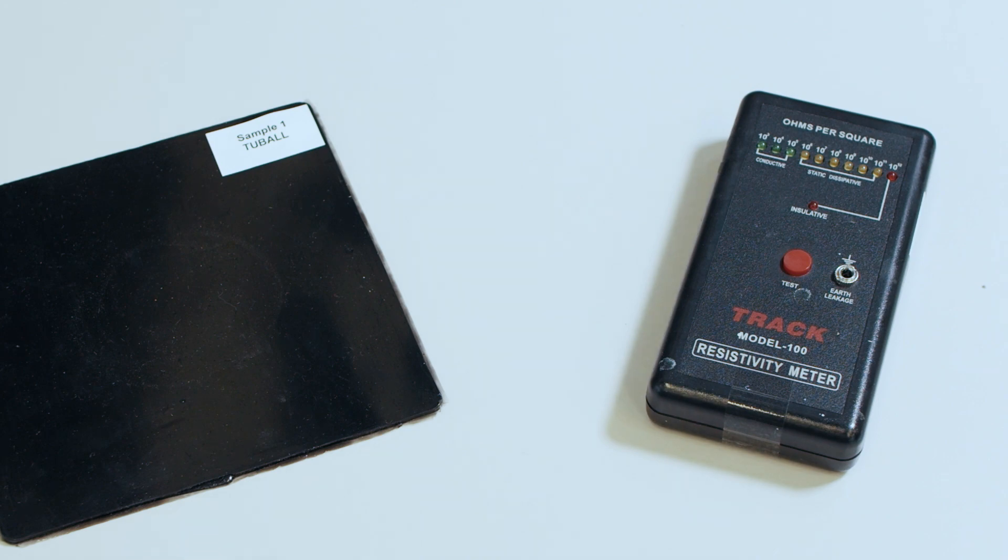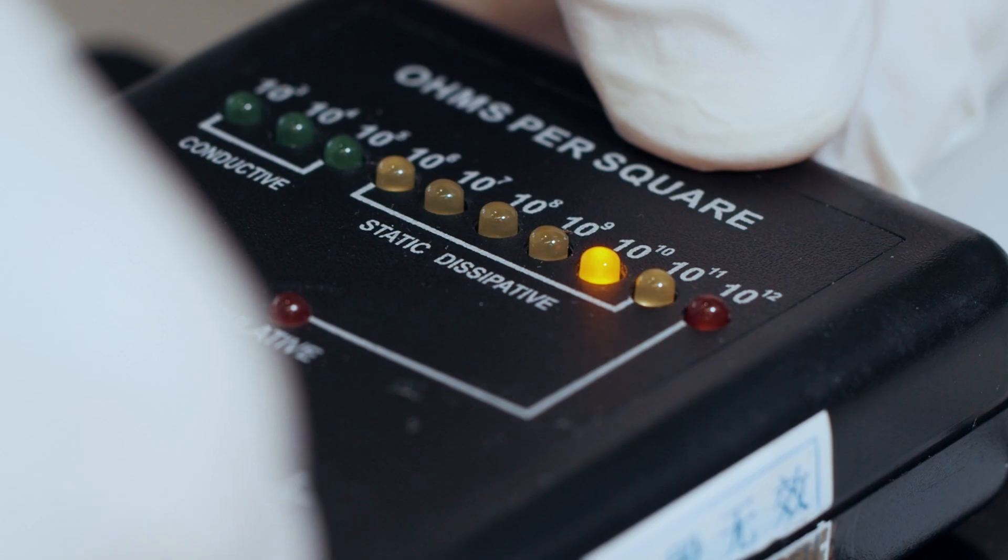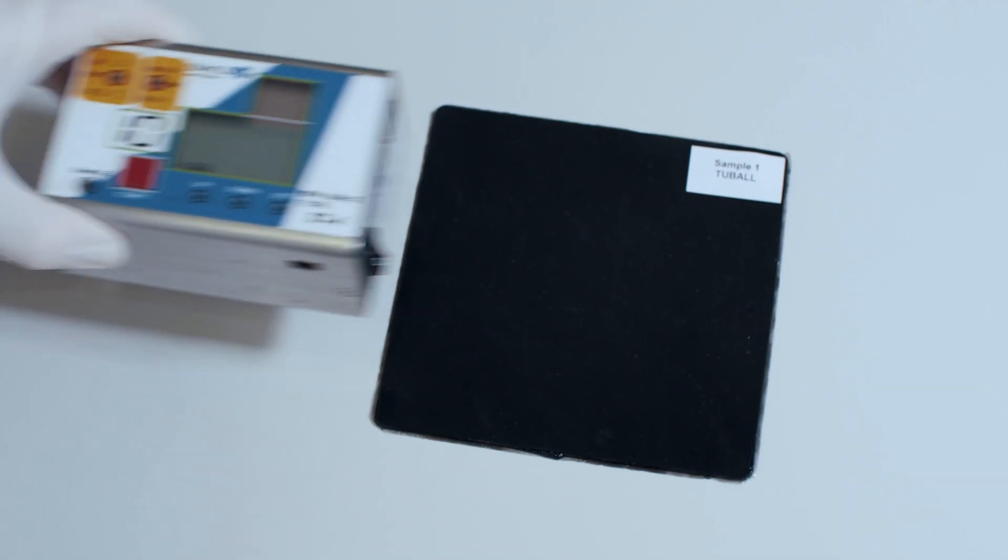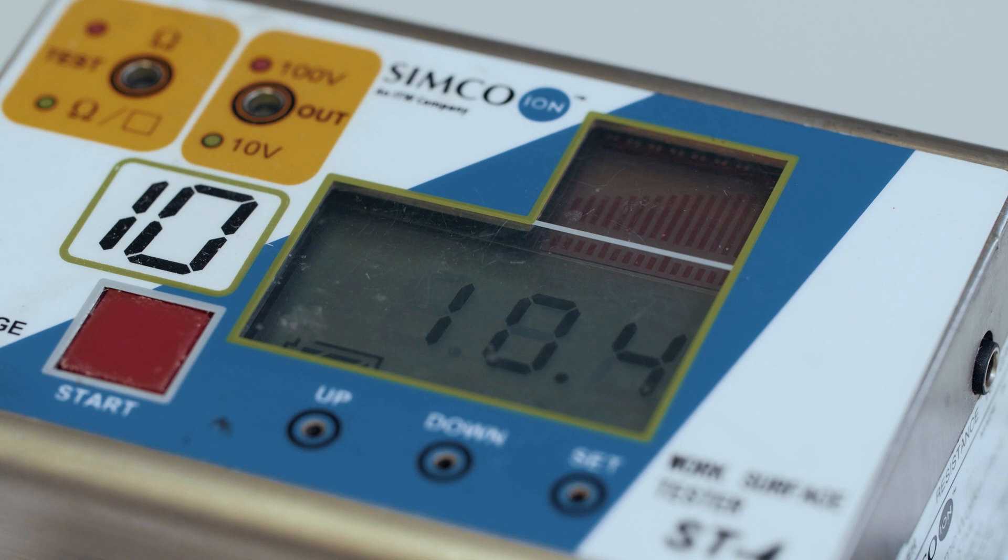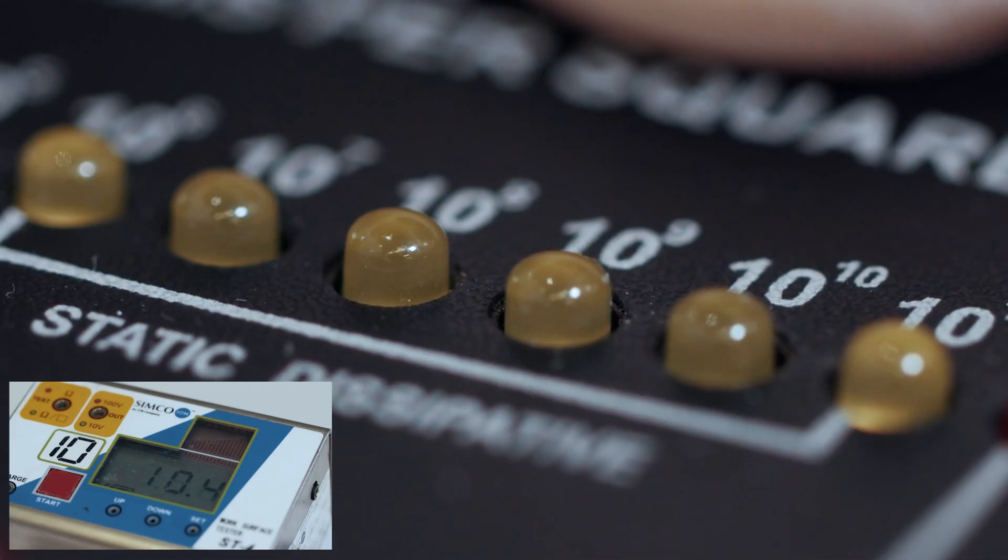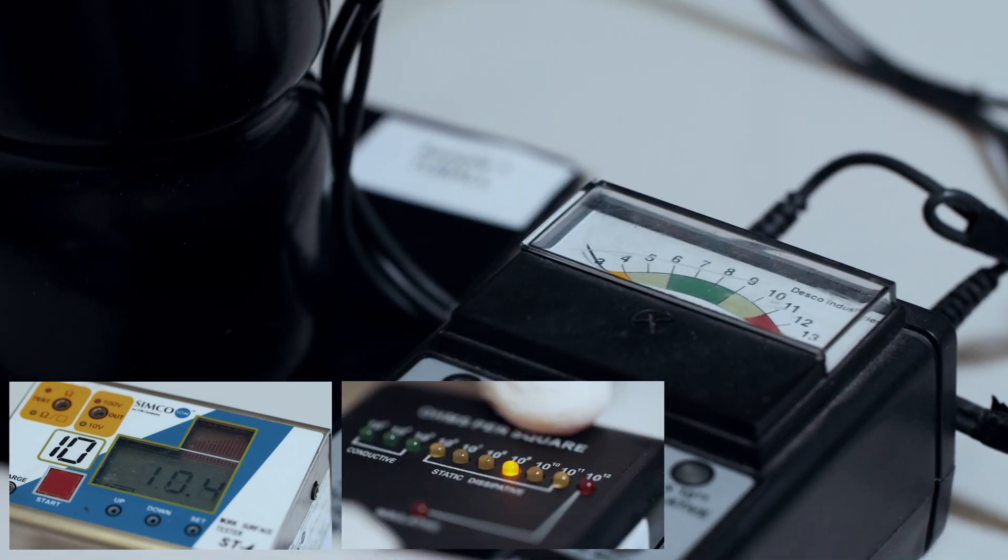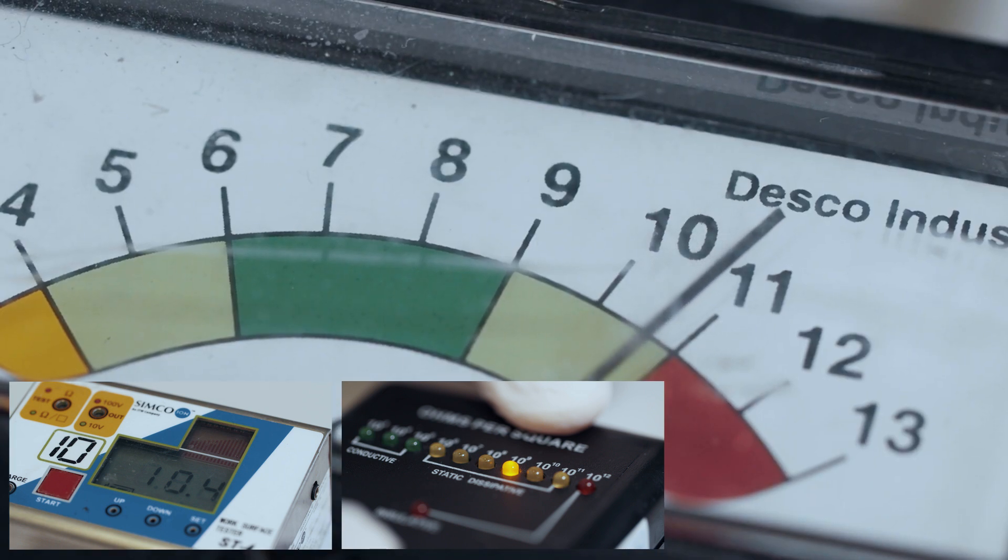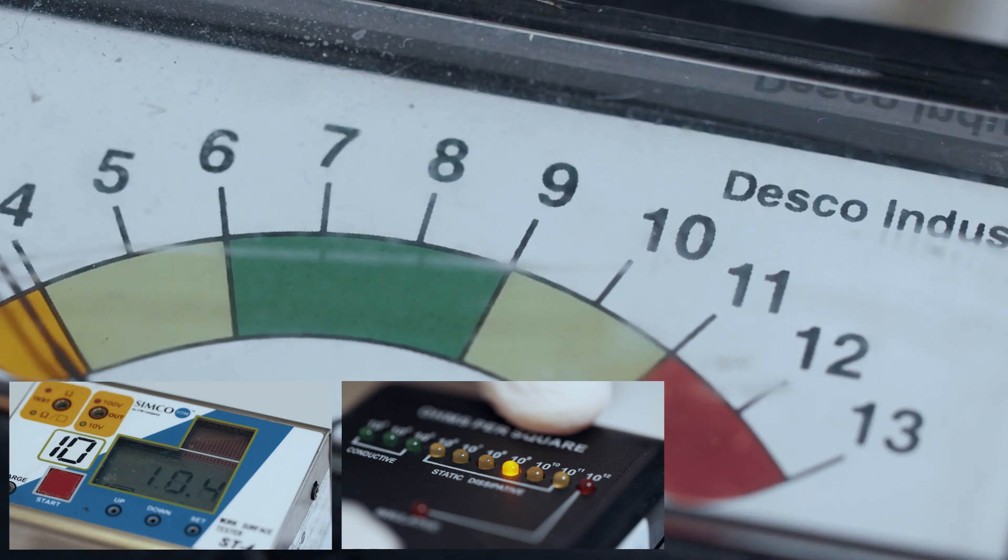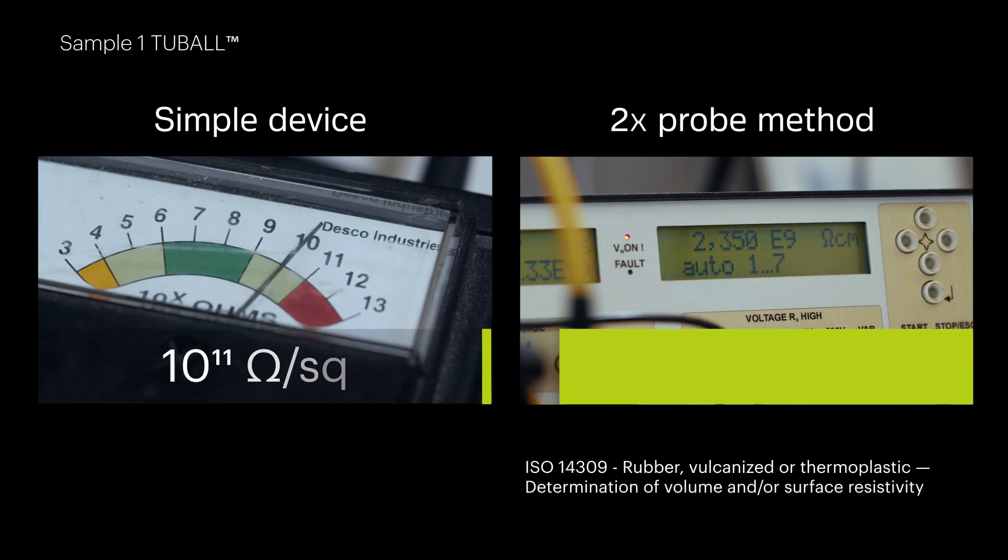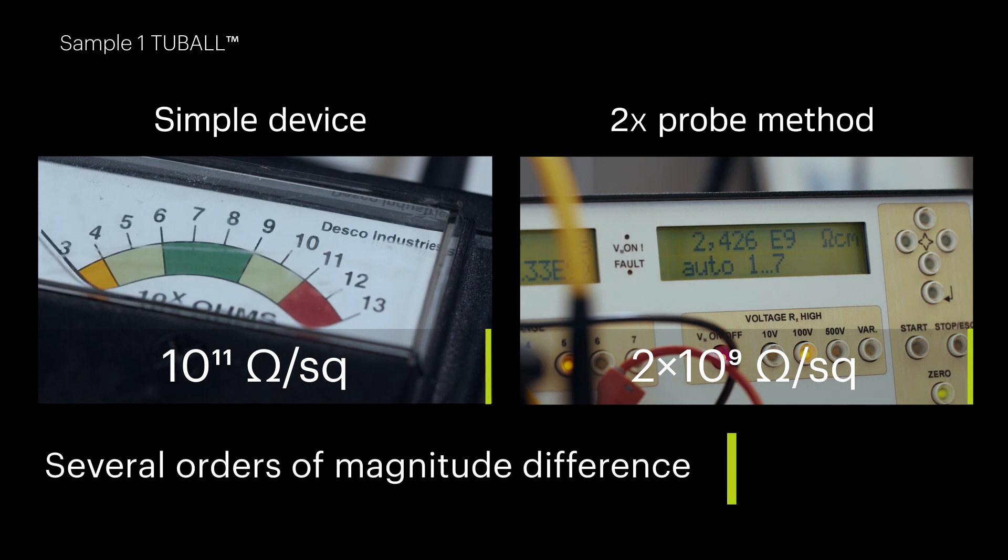To measure surface resistivity, faster alternative methods with so-called simple devices are often used. Let's look at how this works. We should thus bear in mind that the value of surface resistivity obtained using a simple meter can differ from the value obtained using a standard method by several orders of magnitude.